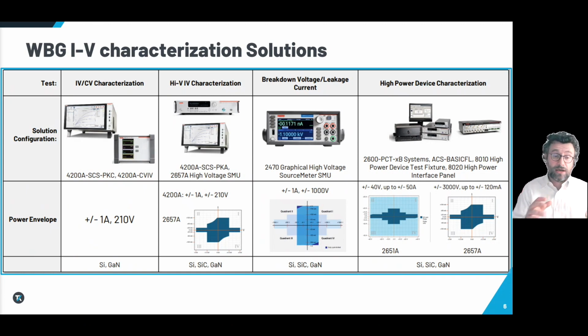Some customers are working on silicon carbide. They need a solution that can collect lots of IV curve data up to 3000 volts. They need configurable power levels. They need wide dynamic ranges. They are measuring from microvolts to kilovolts, or currents from femtoamps to hundreds of amps. And they actually request the setup to be modular. They want the setup to be upgradable in the field very easily and reconfigurable. So our PCT, our parametric curve tracer systems, are actually based on aggregated SMUs. And this can be upgraded easily in the future depending on the needs that you have. And all the individual instruments can be used separately for other applications.